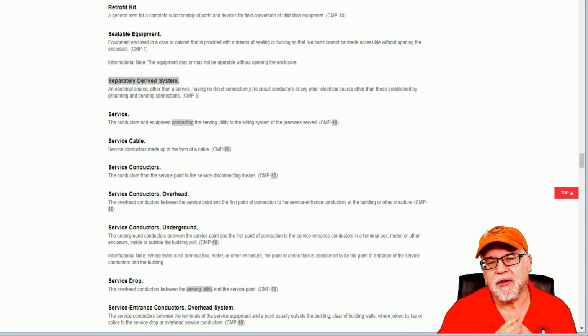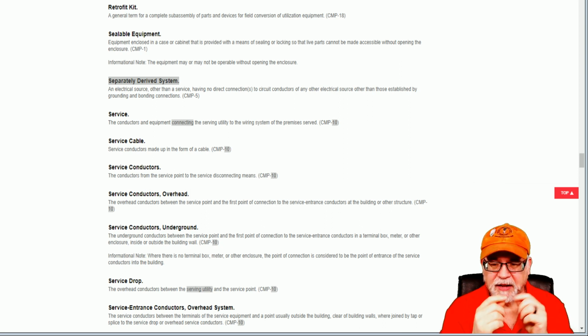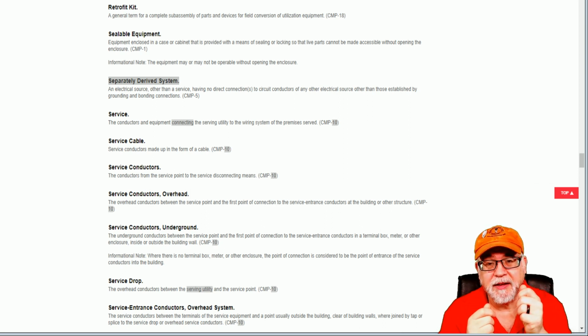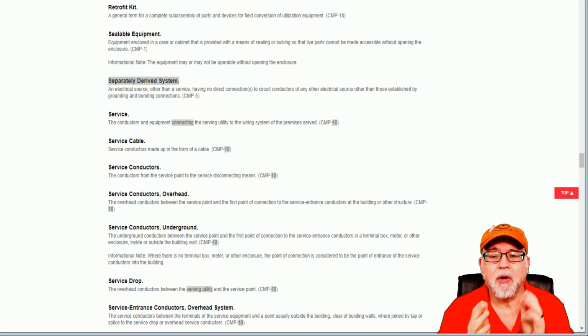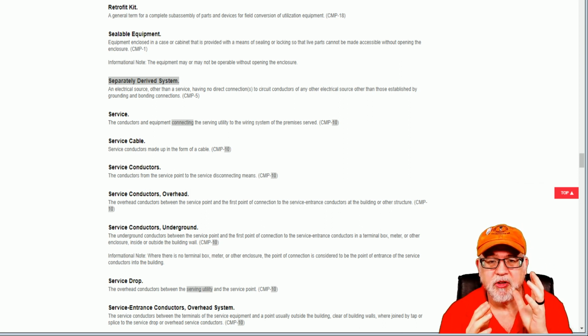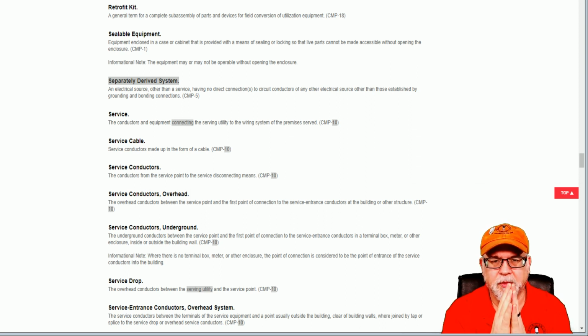Now, a separately derived system, say a transformer: you come into the transformer, you have what's called a primary side, and then you have what's called a secondary side. Those windings are very close, but they have a turns ratio, a number of turns on the primary relative to the secondary. Like if it was 100 turns on the primary and 25 on the secondary, that'd be a 4-to-1 turns ratio. Okay, so again, you understand that the transformer is taking one voltage and changing it to another voltage, but they're not physically touching from primary to secondary. They're very close, but they're usually separated by dielectric material. Okay, so they're very close.